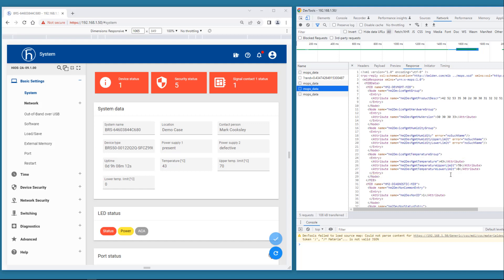So now we know that the MIB variable for temperature is HM2 device management temperature. And it's located in the HM2 device management MIB.